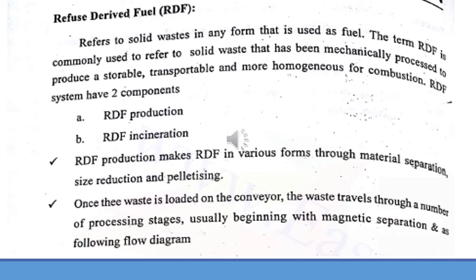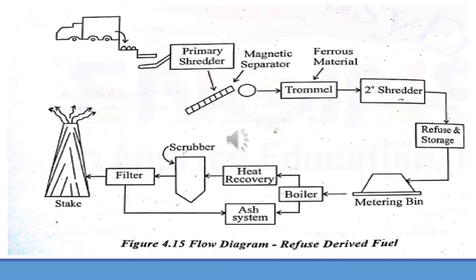Refuse Derived Fuel (RDF) has two components: RDF production and RDF incineration. In RDF production, fuel is produced in various forms through material separation, size reduction, and pelletization. For RDF incineration, a truck dumps all waste into a primary shredder which reduces the size of the waste materials. The waste then moves into a magnetic separator to remove ferrous materials. Again these materials are shredded to the required sizes and move into a boiler where heat is generated, converting waste into ash and heat, which is then used for other purposes.